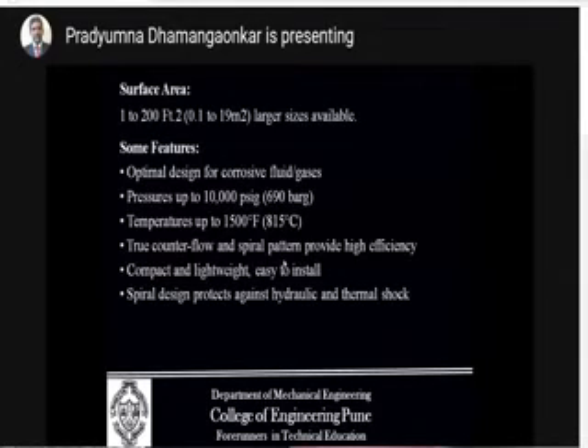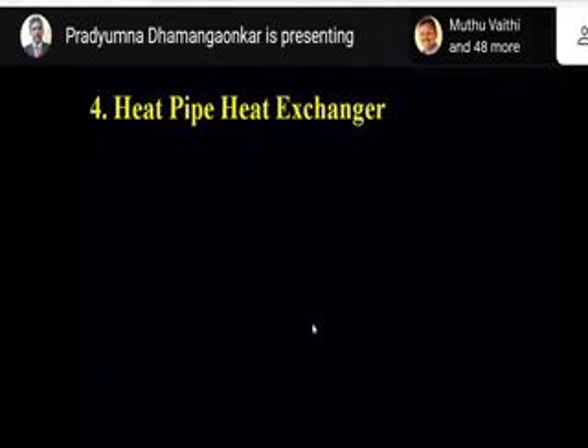I will not go through this. I will concentrate on one very innovative heat exchanger, that is the heat pipe heat exchanger. Nowadays, it is recommended for universal purposes. Everyone knows the vapor compression cycle, which consists of a compressor, condenser, expansion valve and the evaporator. In this vapor compression cycle, the compressor consumes power.